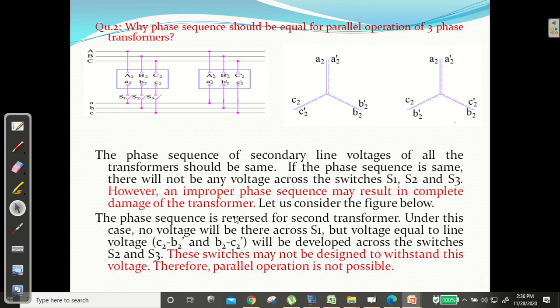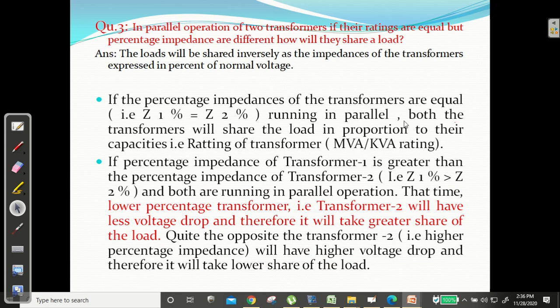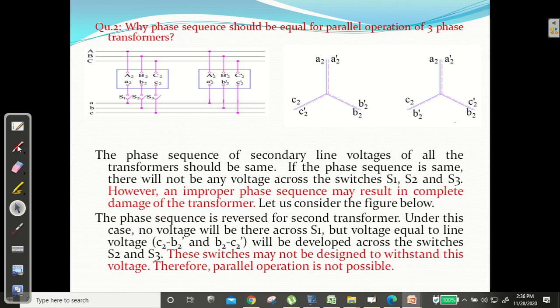Okay, this may happen. Suppose here phase sequence changes, what will happen here? C2 dash and B2 here, because of that voltage will be very high, and because of that voltage circulating current can flow, and dead short circuit will be there, and the switches may not be designed to withstand this voltage, therefore parallel operation is not possible. So phase sequence should be same, be careful about it, right?